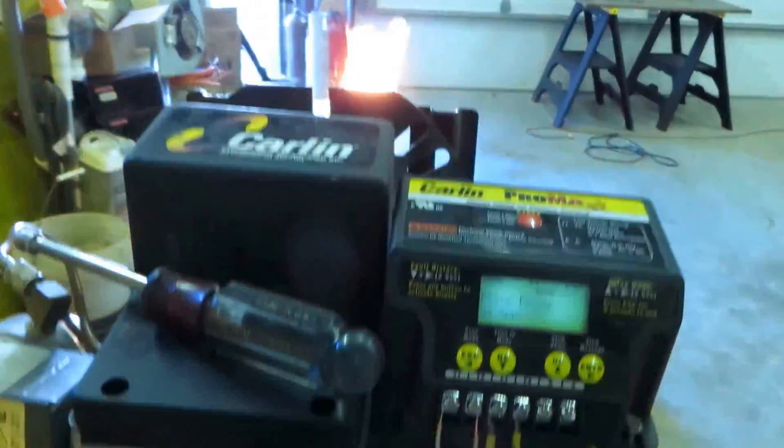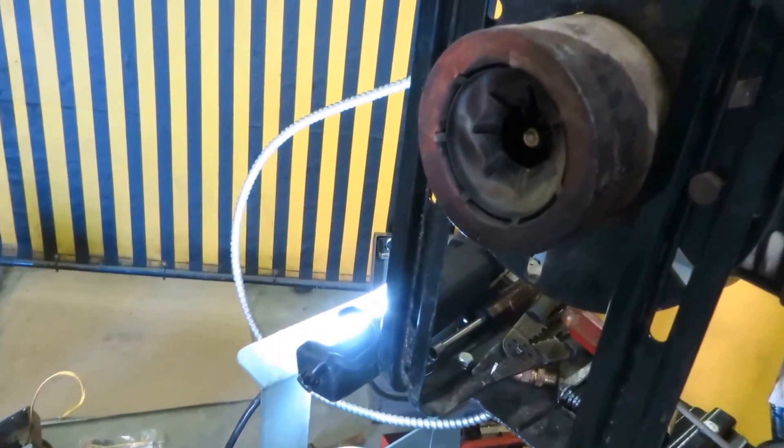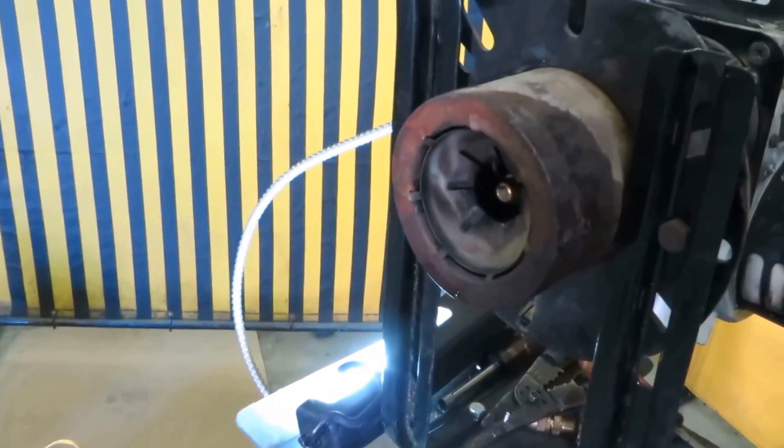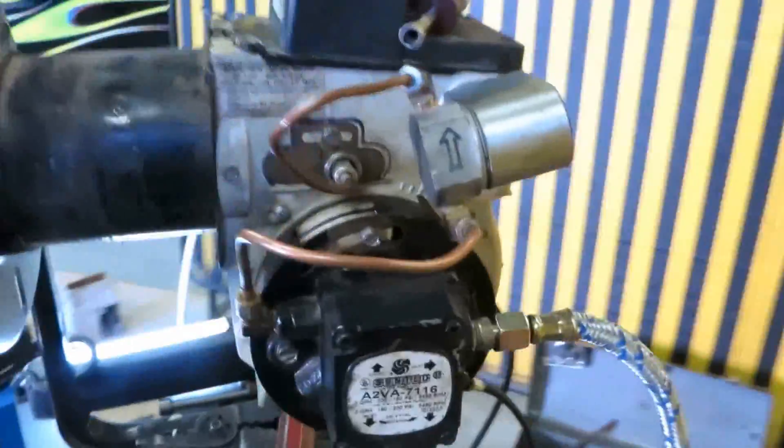Alright, then we'll shut off our limit. It's up to limit, oil is hot, shuts off. Motor delay, I dropped it down to 30 seconds. I'm in post-purge now for 30 seconds to get rid of all the fumes up the chimney. Post-purge will dry this head out. And the burner shuts off.